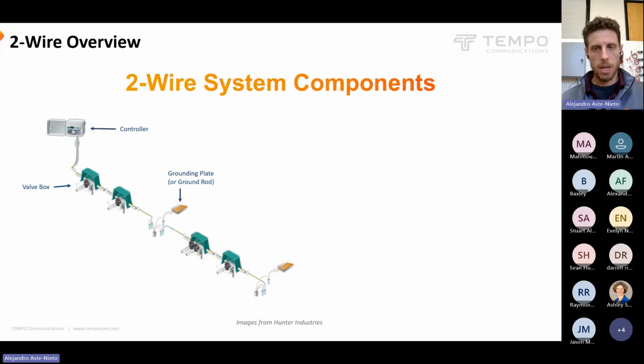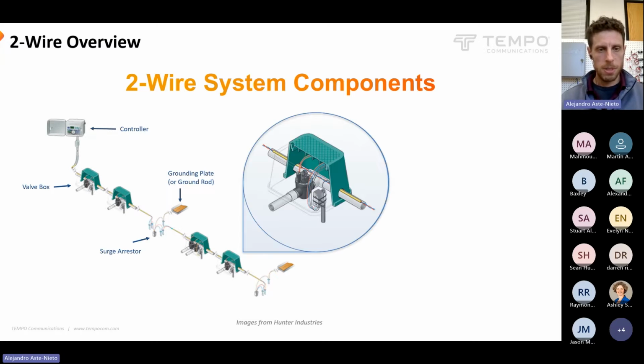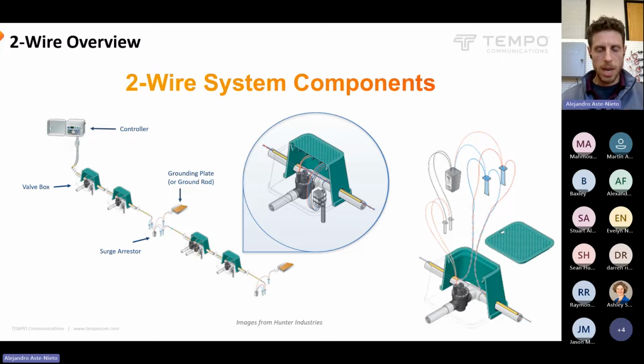It's important that there is grounding every so often, because since this is all just one big linked system, it could all be damaged with just one bolt of lightning. So grounding is important for damage protection. And with each grounding plate or grounding rod, there will need to be a surge arrestor to help redirect voltage away from the valuable components. And then inside a valve box, we have the valve itself.